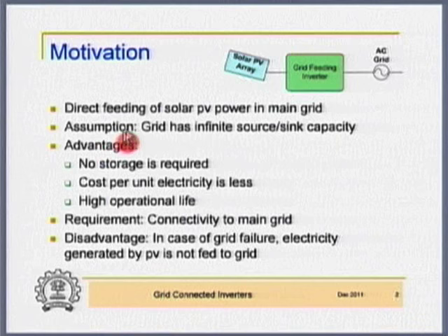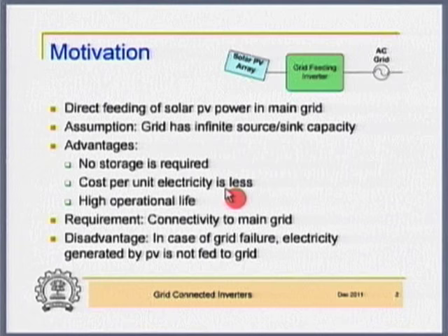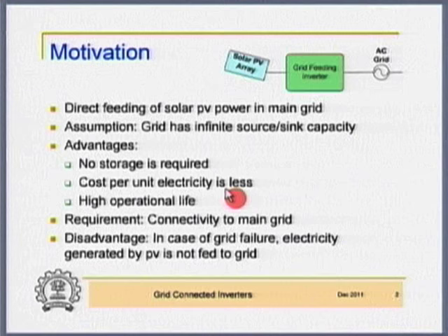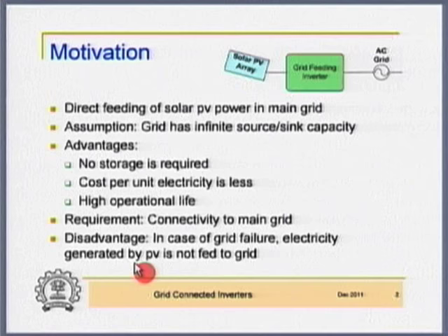Today I will discuss solar grid-connected inverters. The direct motivation is direct feeding of solar PV energy to the main grid. We are assuming that the grid has infinite source or sink capacity. Advantages are: no storage required, cost per unit is less — battery is one of the most expensive components, and lead acid batteries last not more than 2 to 3 years. High operational life is achieved when connected to the main grid.